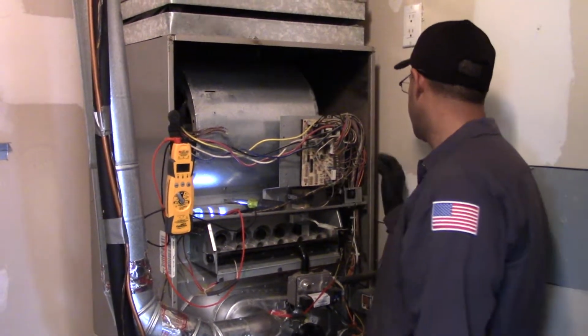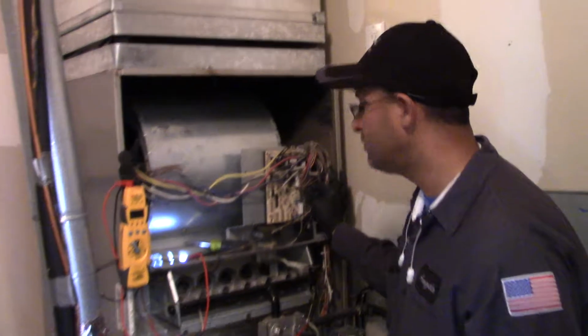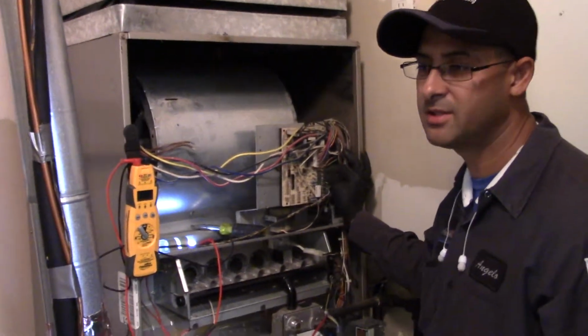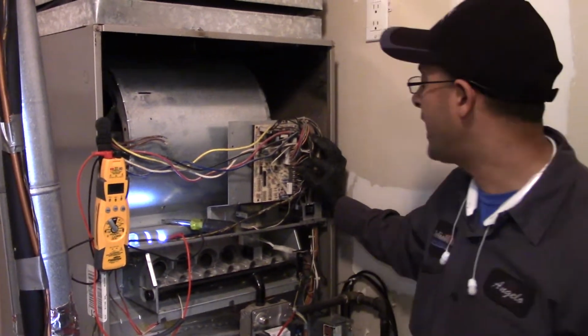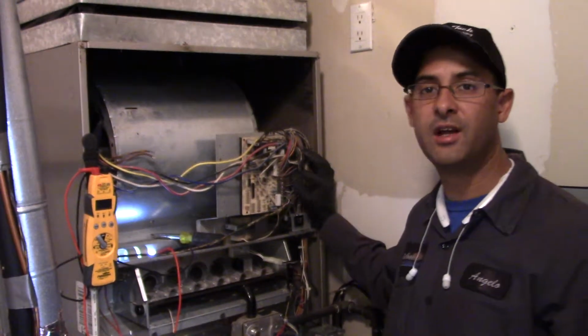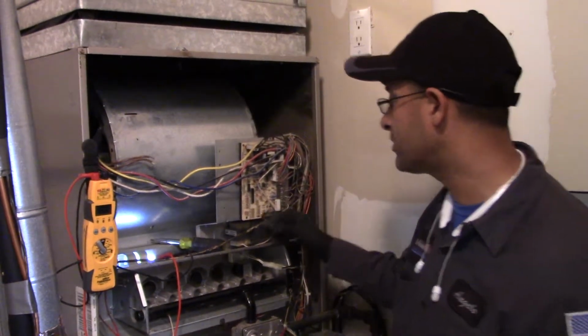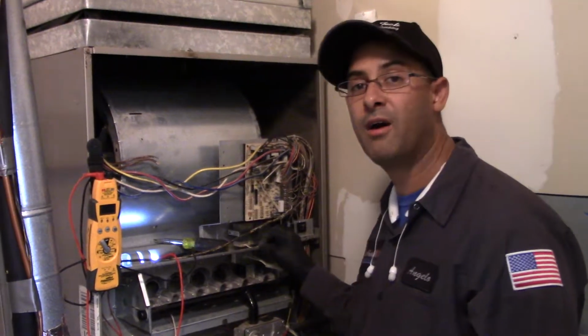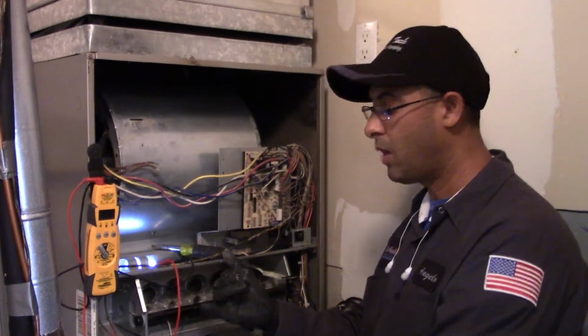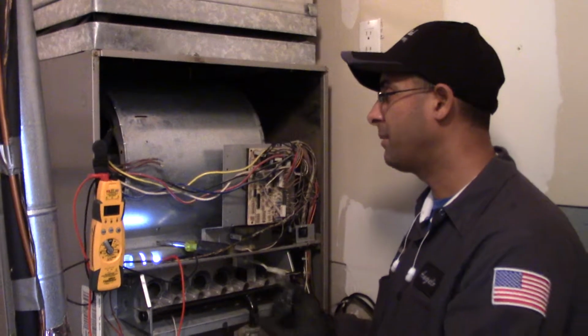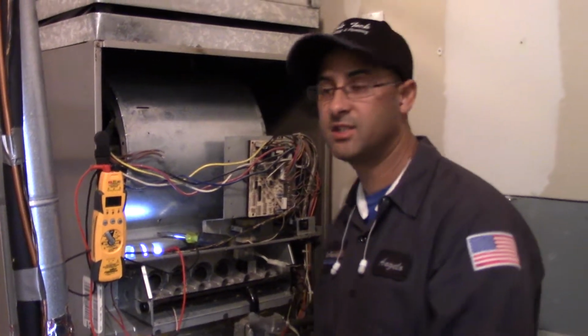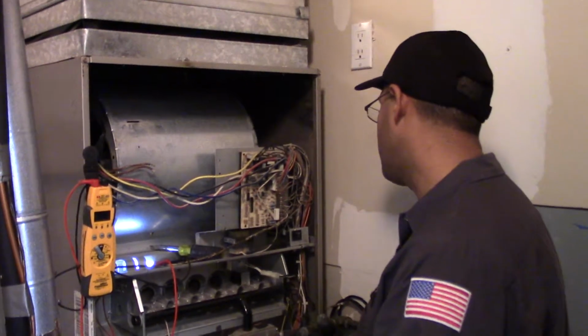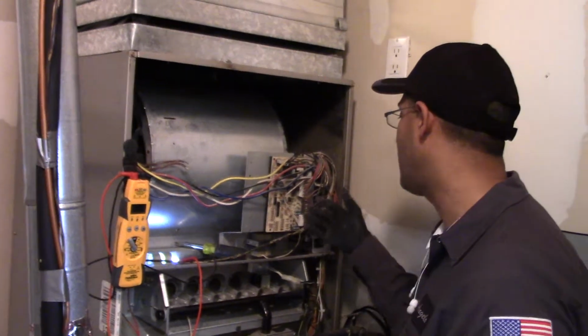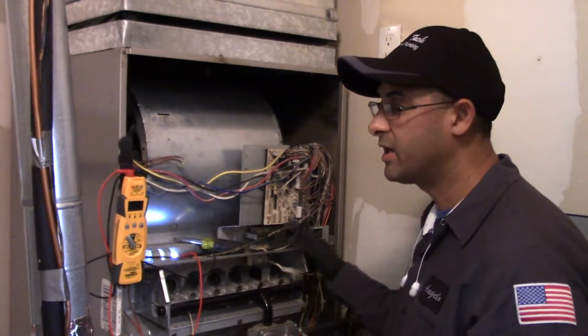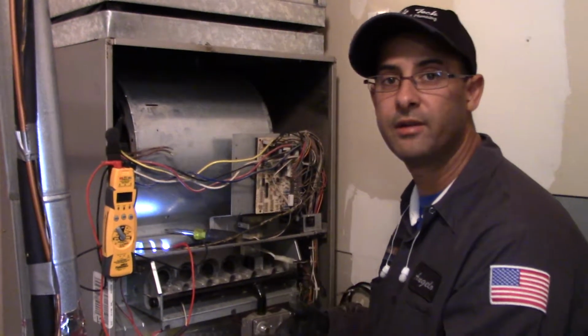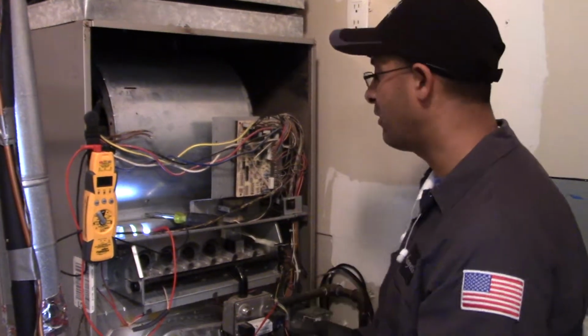Okay, and also on this board we have a fuse. This is our 24 volt fuse. If that was popped, then I probably have a nick on the wire, or the wire's touching metal somewhere. So I want to find out why that fuse popped, what went bad. It's more than likely I have a short in the system that I have to find, and the way to do that is ohming out the thermostat wires, and we'll look at that in a second.